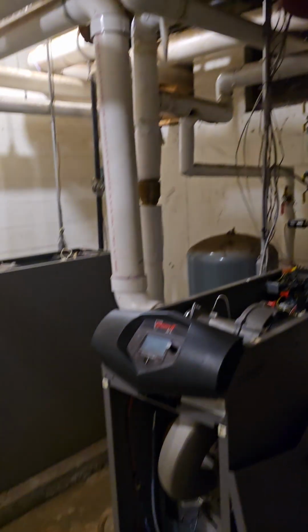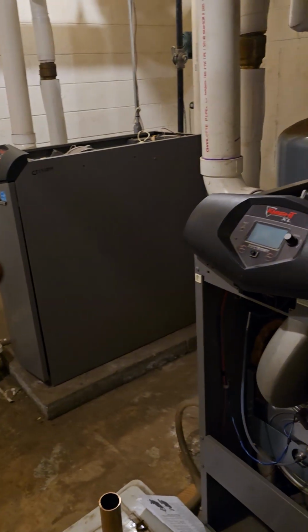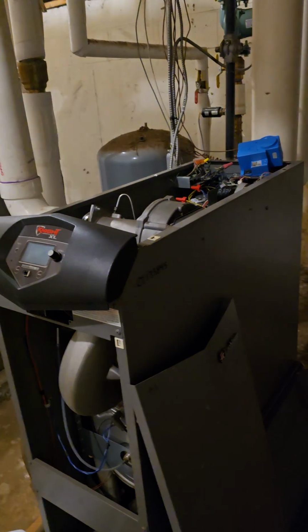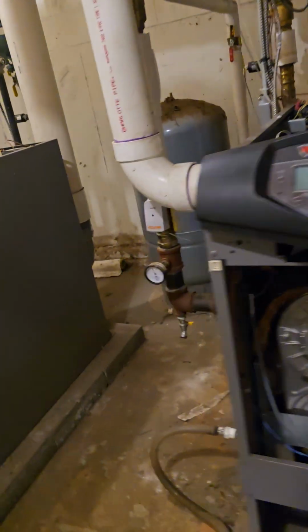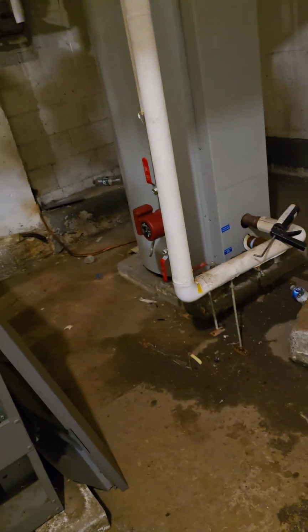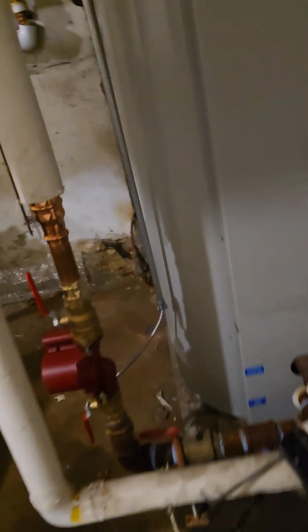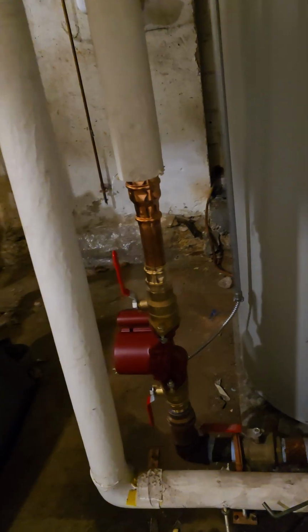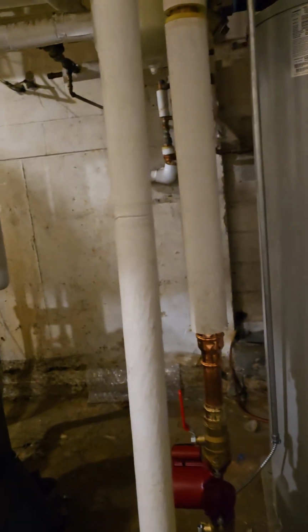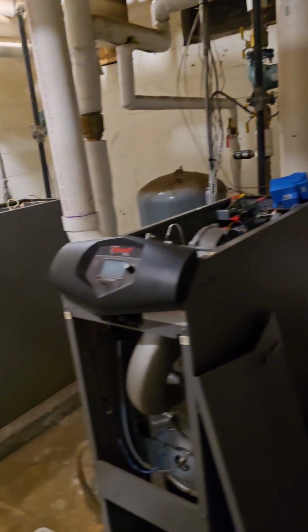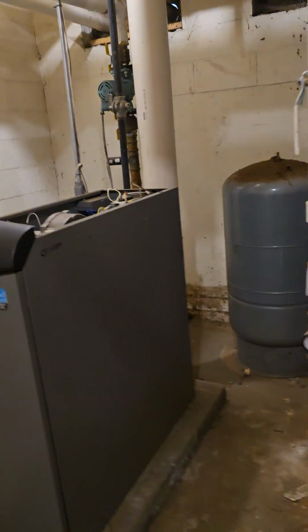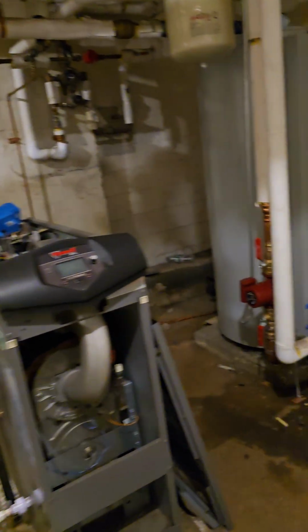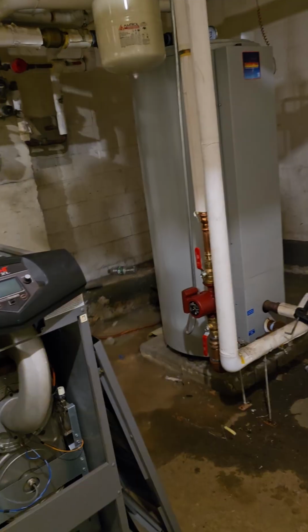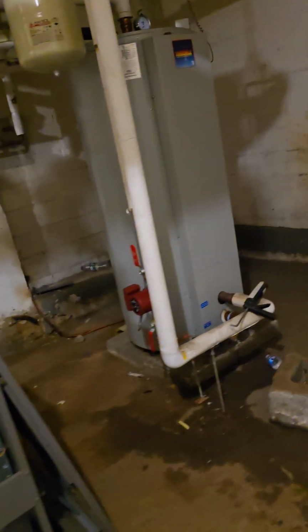A bunch of 2-inch pipe. The only head loss I really have is through this heat exchanger, and I'll explain why. So the head loss was nothing, and all I need is 32 gallons a minute to satisfy this tank. Reading pump curves is super easy. Now, are you supposed to take every fitting and deduct it? Yes. Head loss in feet of pipe? Yes. With 2-inch pipe, typically there's very little head loss unless you get into higher flow rates, but this is an emergency repair at any rate.